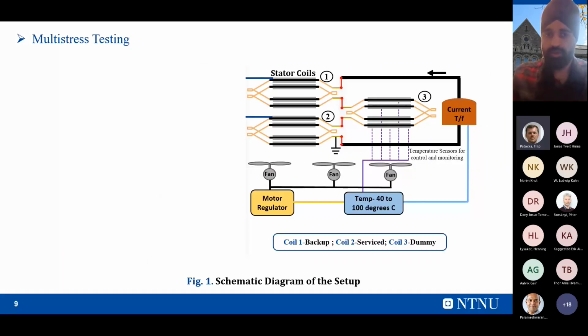In the next slide, I'll show you this. The right side part I have shown right now is only a thermal effect. We are providing only the thermal effect. So this current transformer will feed a current of about 1500 amperes based on the rated values. This current will create I squared R, basically ohmic losses. A huge amount of current will flow, but the voltage of this current transformer is only about 1 or 2 volts. So basically it is not a voltage transformer, it is a current transformer, and it is only feeding a current at very low voltage.